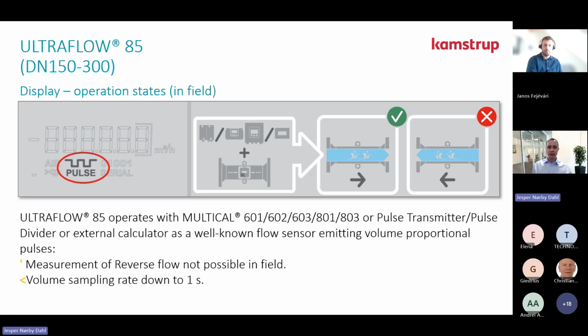If it works with a different calculator, one of the other PCB types, or one of our pulse dividers or a third-party calculator, then the display of the flow sensor will write a simple message saying, I am working in pulse mode together with the calculator. It's very important to say that when working in pulse mode, it is only forward flow. Reverse flow is not supported.